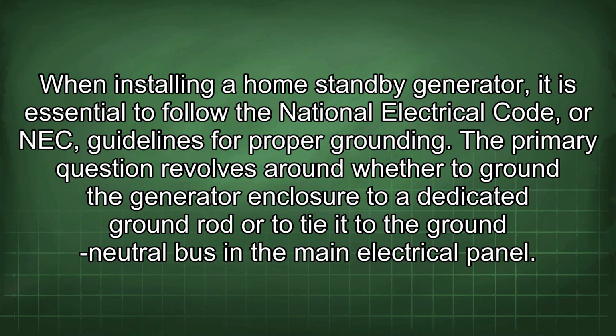When installing a home standby generator, it is essential to follow the National Electrical Code, or NEC, guidelines for proper grounding. The primary question revolves around whether to ground the generator enclosure to a dedicated ground rod or to tie it to the ground neutral bus in the main electrical panel.